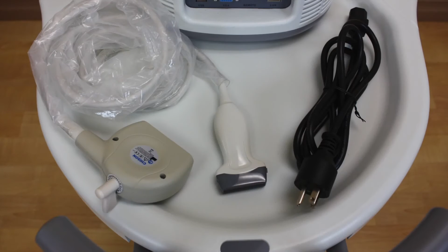Before installing the power cords, probes, or other accessories, it is important to consider the environmental conditions that the ultrasound will be operated under. The working environment should have an approximate temperature range of 5 degrees to 40 degrees Celsius or 41 degrees to 104 degrees Fahrenheit, and a relative humidity range of approximately 30% to 80% with no condensation. The ideal atmospheric pressure would range from approximately 700 to 1060 HPa.